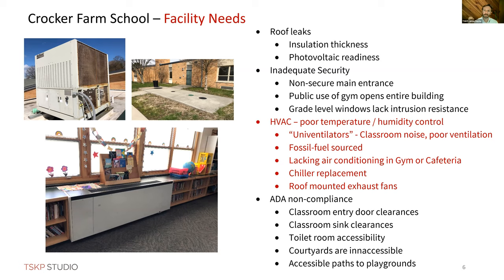Air conditioning is not currently provided in the gym and cafeteria. As we need to replace the chiller in this project, we can also extend it to provide air conditioning in those spaces. Also, roof-mounted exhaust fans are in bad shape and should be replaced in the next few years, so we'd recommend doing that as part of this project.